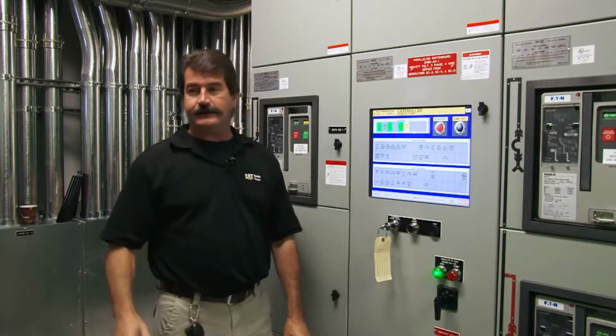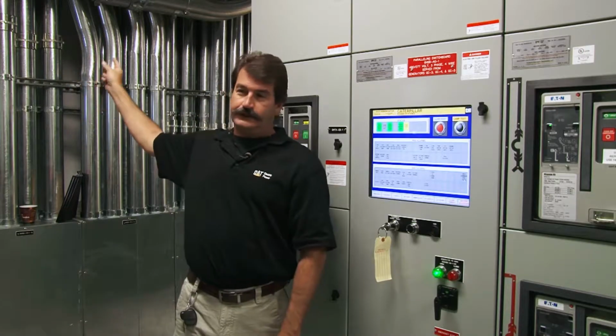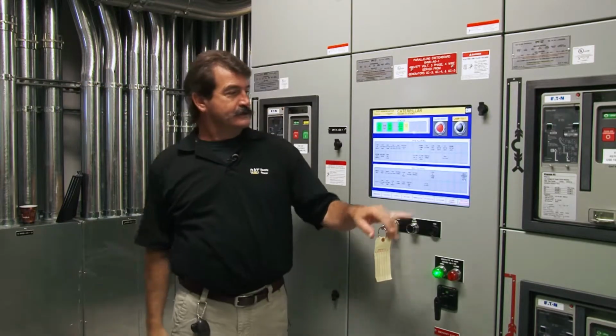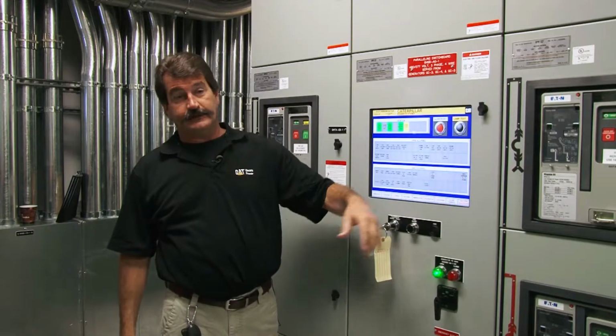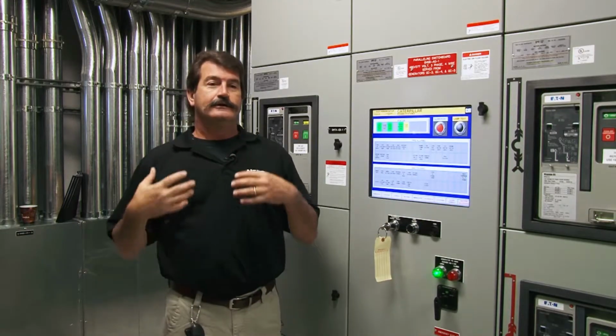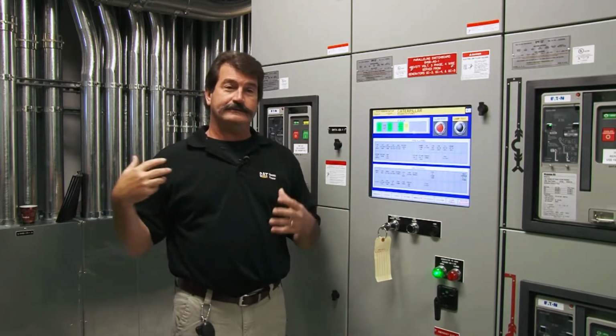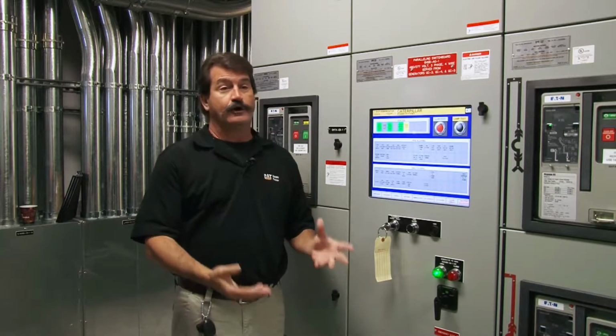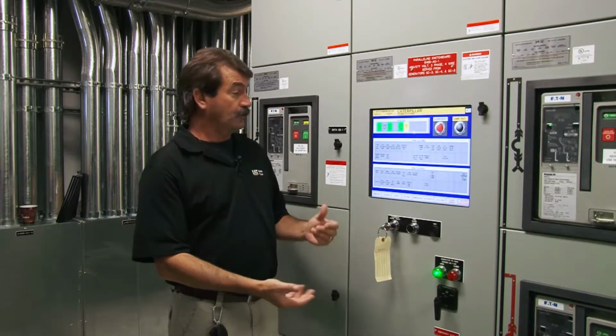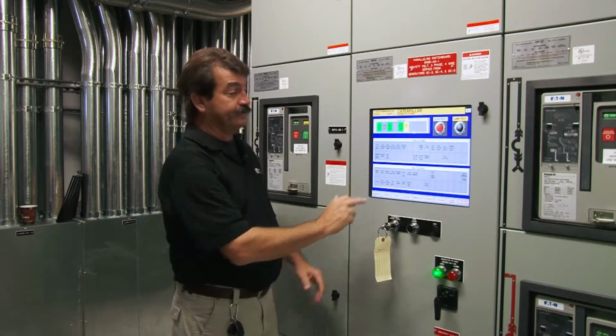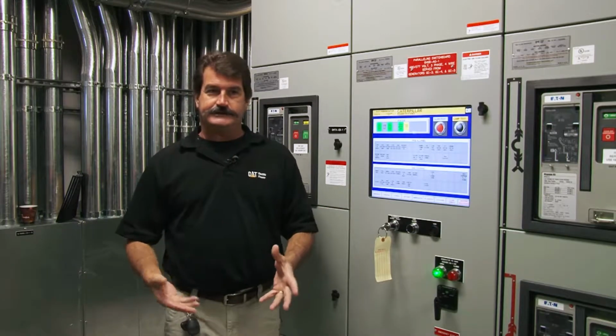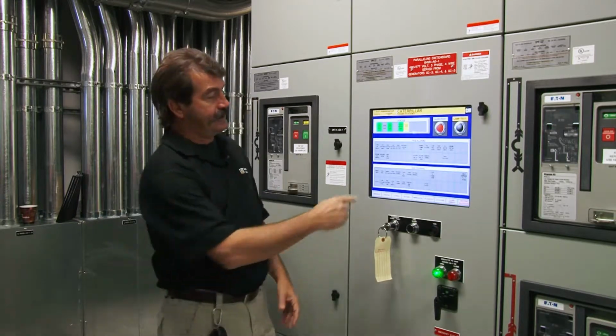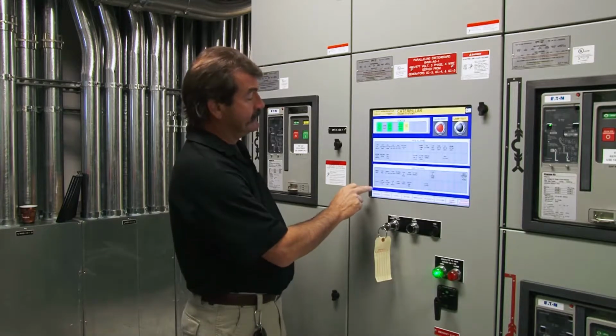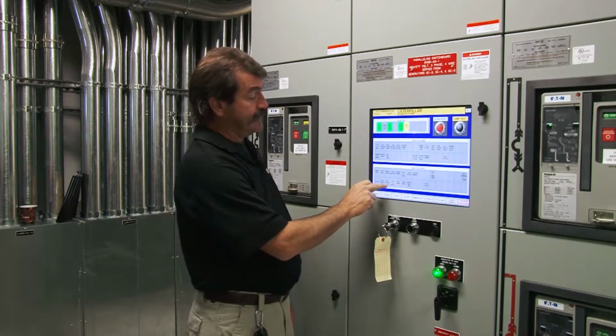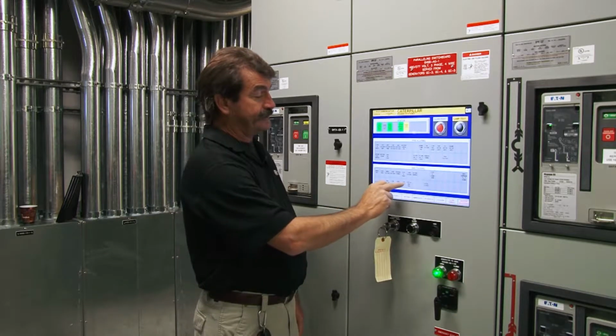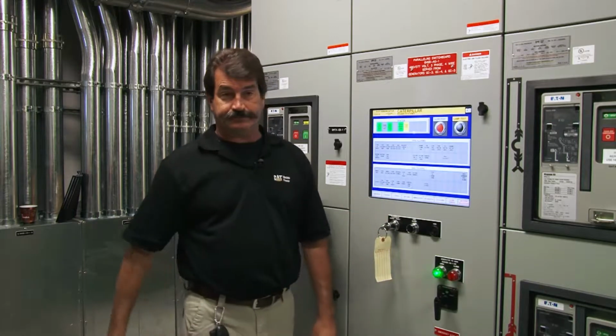EMCP summary shutdown: if that shuts down for any reason, that's a hardwired alarm right there. It'll come in and say, look, you've had the EMCP shut down the generator. We don't know why, or we might know why. It might be one of these, but that's just letting you know that it's shut down out there and not inside here, okay? It might have been low coolant level, high coolant temp, all this stuff right here, that's all at the gen, okay?